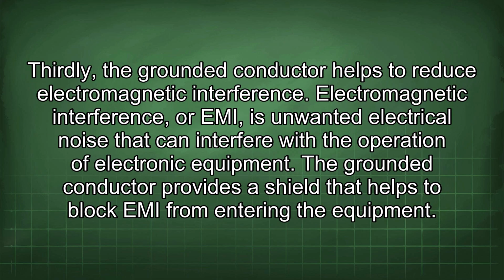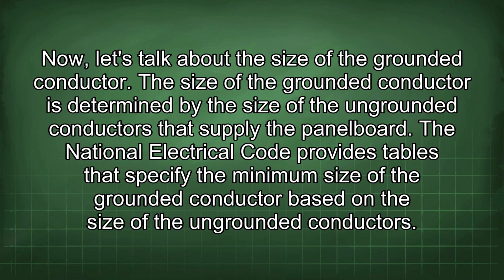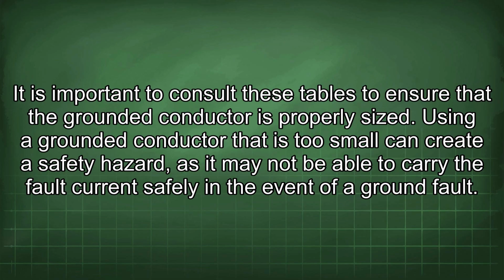Thirdly, the grounded conductor helps to reduce electromagnetic interference. Electromagnetic interference, or EMI, is unwanted electrical noise that can interfere with the operation of electronic equipment. The grounded conductor provides a shield that helps to block EMI from entering the equipment. Now let's talk about the size of the grounded conductor. The size of the grounded conductor is determined by the size of the ungrounded conductors that supply the panelboard. The National Electrical Code provides tables that specify the minimum size of the grounded conductor based on the size of the ungrounded conductors. It is important to consult these tables to ensure that the grounded conductor is properly sized. Using a grounded conductor that is too small can create a safety hazard, as it may not be able to carry the fault current safely in the event of a ground fault.